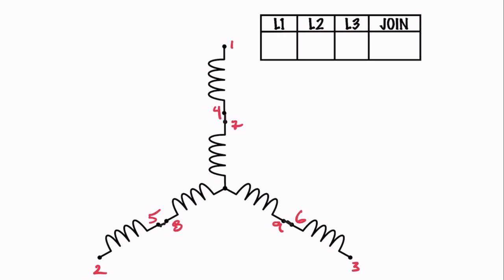Line one connects to lead one, line two connects to lead two, line three connects to lead three. Then for our joining points: we connect four and seven together, five and eight together, and six and nine together. And we're done — we've got it all connected up for the higher voltage.